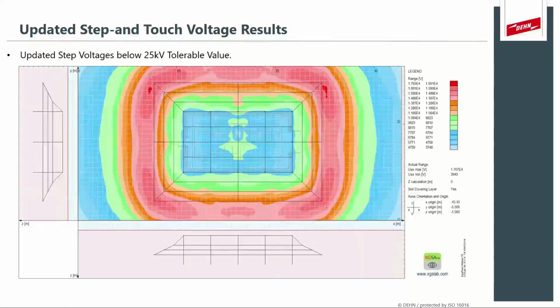If we look at it then from the top, we can see that this is a graph now of the step voltages and of the ground potential rise itself. You can see that we do not exceed the 25 kilovolt limit that we were aiming towards. And the system is then also safe against step voltages.